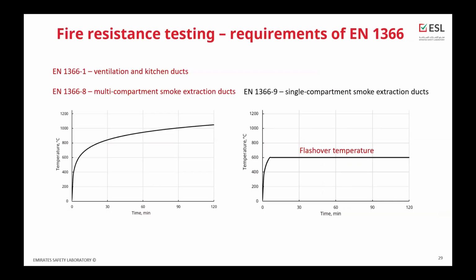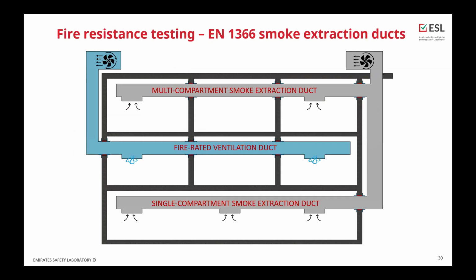If we are talking about the EN standard, we have 2 conditions inside the furnace. We have the same conditions as BS for ventilation, kitchen, and multi-compartment duct. Plus, we have a lower temperature for the single compartment duct, and this is your legal point to get a low temperature fire-rated duct classified and certified. But this will be limited to the single compartment smoke extraction duct, which serves only one compartment. This is just to remind you how the single and multi-compartment ducts look in the building.